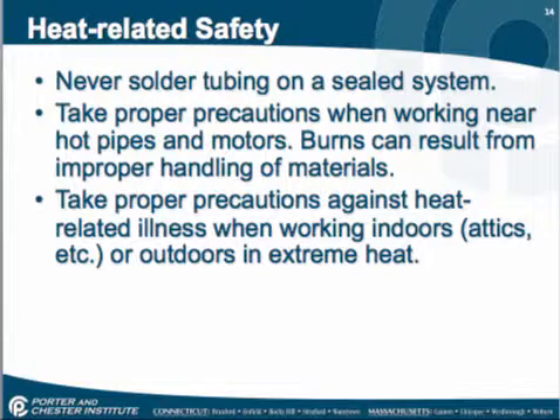Never solder tubing on a sealed system. Make sure if you're soldering something on a system, you have something open, because pressure can build up in a sealed system, and when it does, it's going to blow the hot liquid solder out at you. You don't want that to happen.